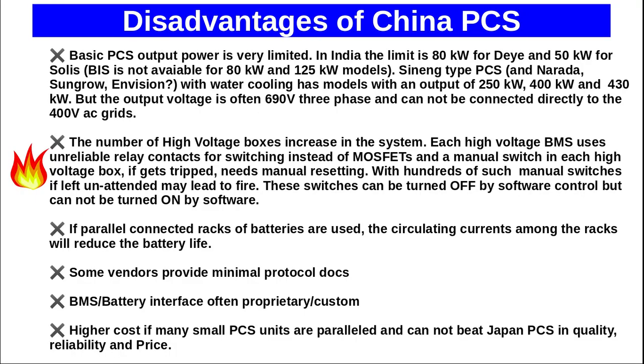What are the disadvantages of a China PCS? Number 1, the maximum power capacity of a PCS is limited to 80 kilowatt for Deye and 50 kilowatt for Solis. We may have power levels of 250 kilowatt, 400 kilowatt and 430 kilowatt in the case of Sineng Energy type of PCS. But the disadvantage there is the AC output for 3-phase is 690 volt and not 400 volt. So we cannot connect these PCSs in parallel to the grid.